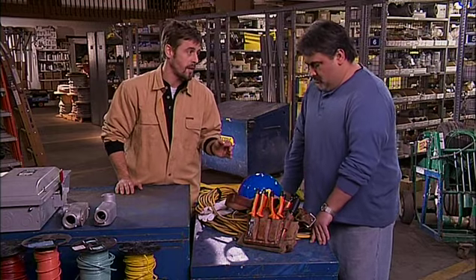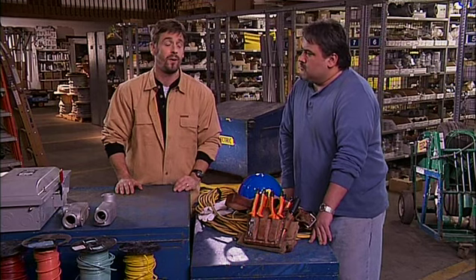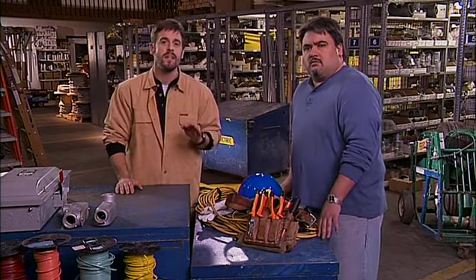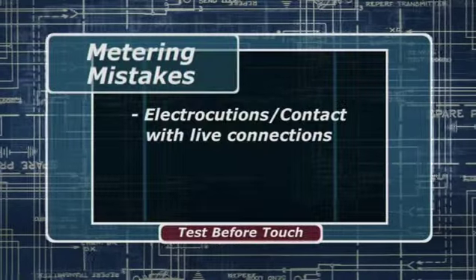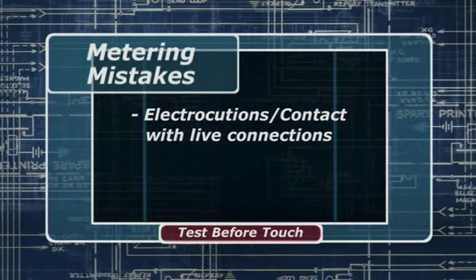Okay. Now, no matter where you're working, whether it's in a large manufacturing plant or on a small installation, when the job involves equipment that could be energized, always test before you touch. Electrical measurements are a routine part of the job for many electricians and maintenance technicians. But if your meter is malfunctioning or it isn't used properly, you could be seriously injured or even killed. Are you serious? Seriously. Now, when you take electrical measurements, the system needs to be energized. Your meter and test leads are connected to a source of energy, and mistakes can have disastrous consequences, such as electrocution from contact with exposed live connections at the test probes or plugs.